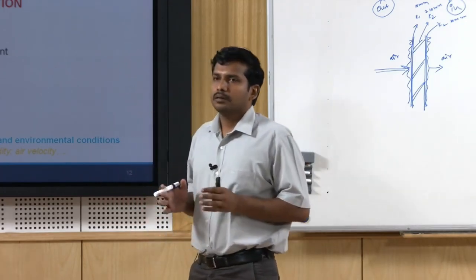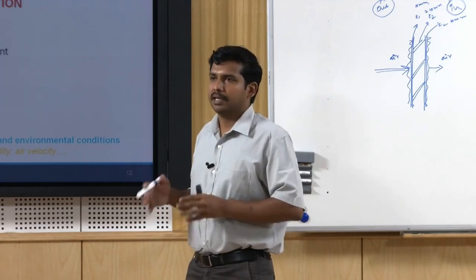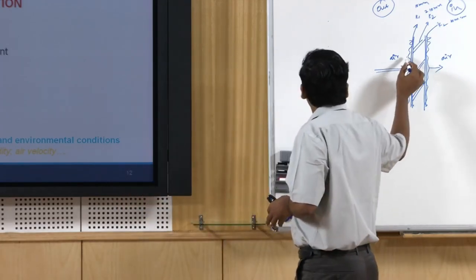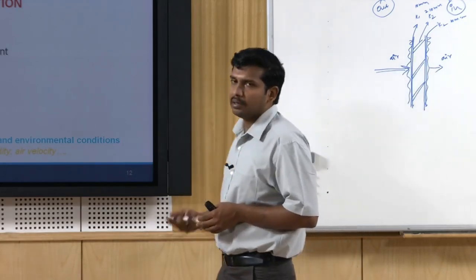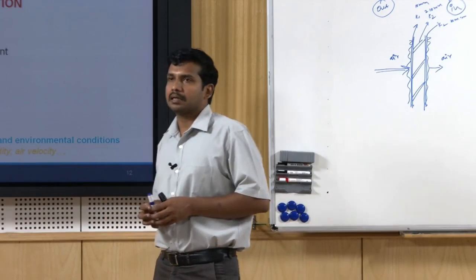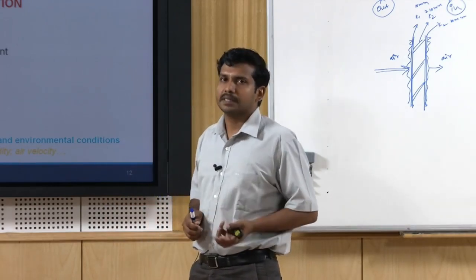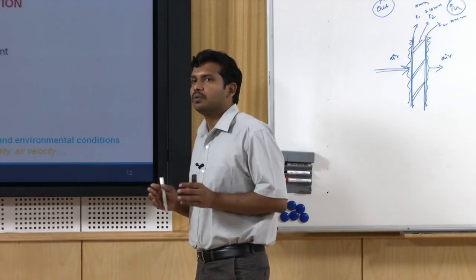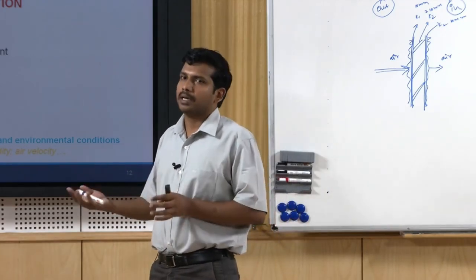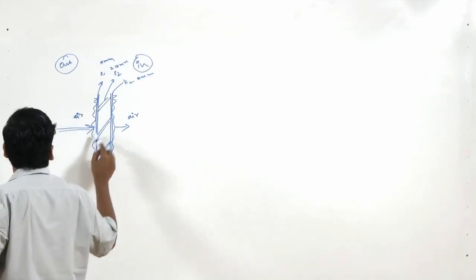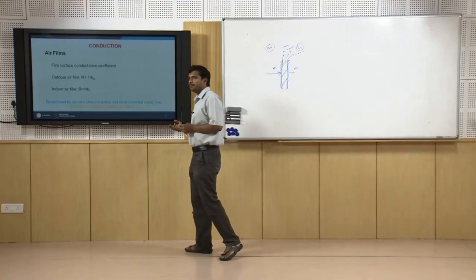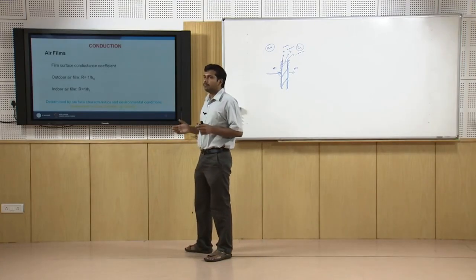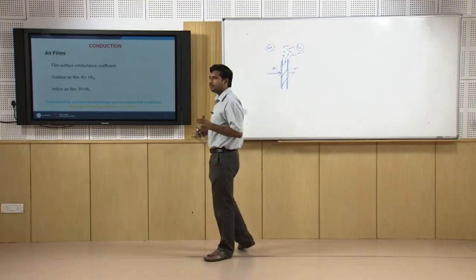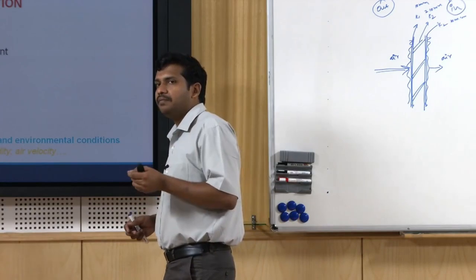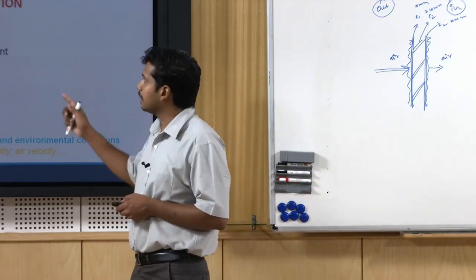But for total building calculations or load calculations, say heating and cooling load, the impact of these film coefficients and the changing U value because of these ambient as well as surface characteristics is roughly about 4 to 5%, though it is still being researched. That is not a heavy impact compared to the other contributors. Say, when I want to introduce an insulation here, the effect of this versus the effect of insulation is considerably different. The insulation has a very high impact compared to the change in film coefficient. So often it is ignored, but still, as a scientific number, it has a good amount of significance in the calculation of U values.